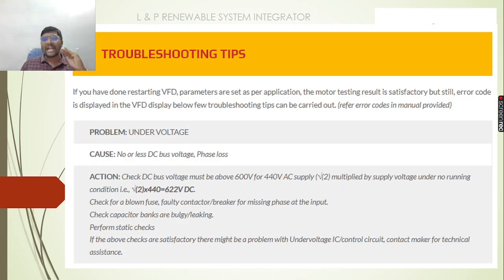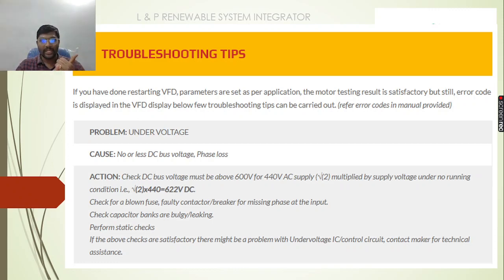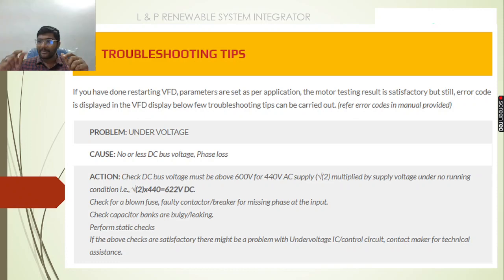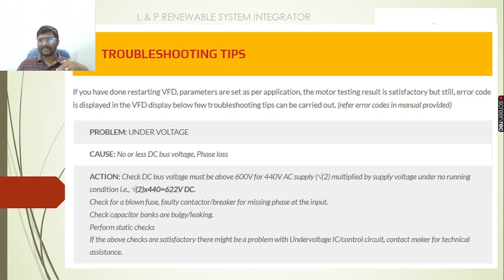Next, if we have an undervoltage problem, what will be the cause? There will be less DC bus voltage or a possibility of phase loss. The first thing to check is the DC bus voltage. For example, for 440-volt conditions, check whether any fuses have blown and check for faulty contacts or a breaker with a missing phase at the input. Check the capacitor banks — whether they are bulging or leaking. After performing all these static checks, if the problem still exists, it is better to contact the technical persons.